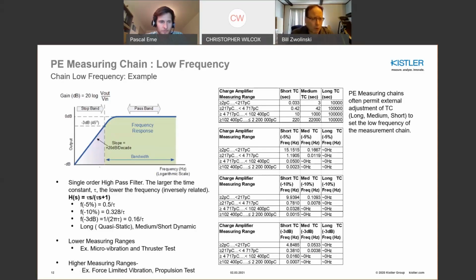The important takeaway here is really when you put forth your measuring chain, you want to ensure that the low frequency characteristic as well as the high frequency characteristic is accommodated by your signal conditioning. So it's important to take a look at that, because a lot of times in charge amplifiers, the actual time constant or the low frequency characteristic could be a function of the actual measuring range selected. So it's always important to pay proper attention to that to ensure that your measuring chain has full coverage over the frequency band of interest.